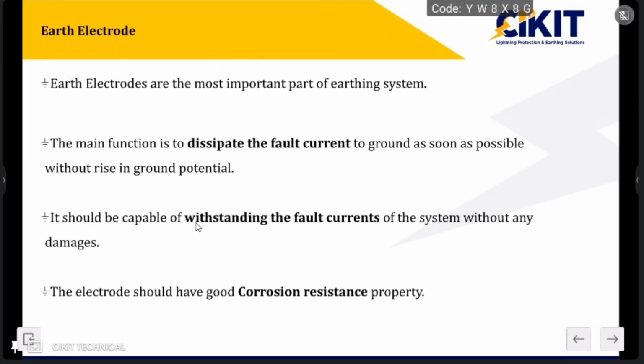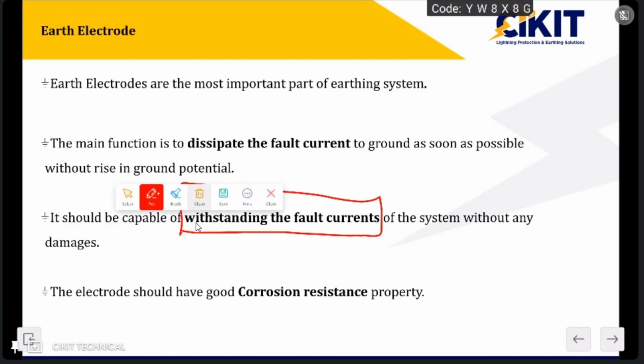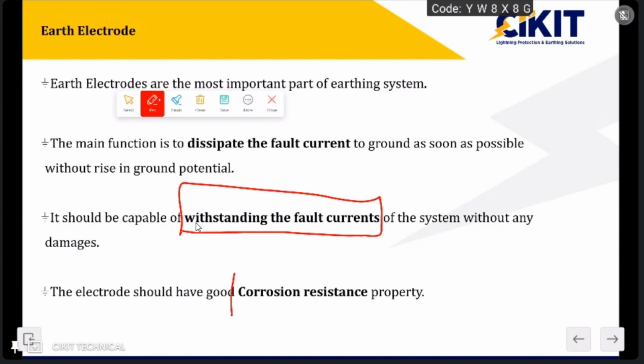If we take earthing, the most important component is the earth electrode. The purpose of the earth electrode is to dissipate the fault current into the soil. To dissipate it, it should be able to withstand the fault current without any damage. So proper sizing calculation should be done for selecting the size of the earth electrodes. It should withstand the fault current, and most importantly, it should have good corrosion resistance.